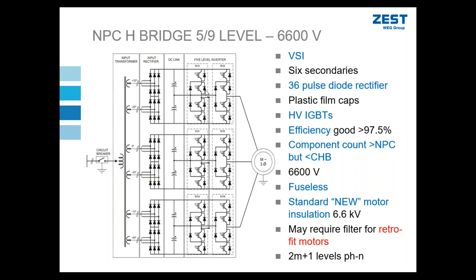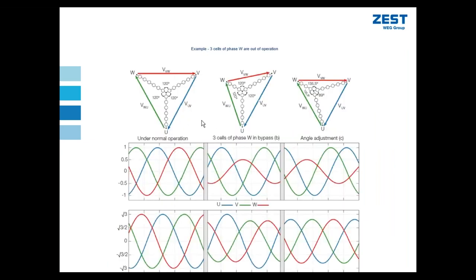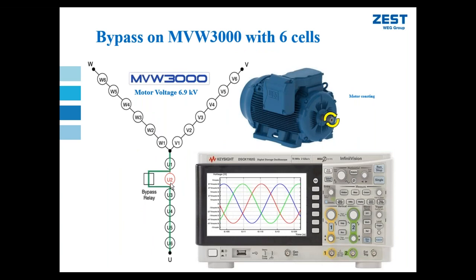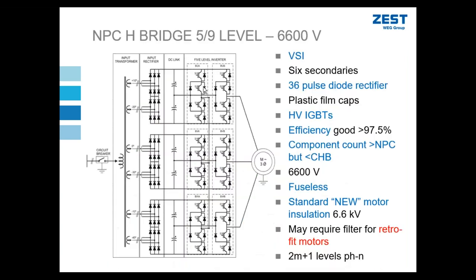Also, I don't have a simple bypass. The bypass here is simple because I'm only bypassing a 690 volt power cell. Here, I'm dealing with much higher voltages. Here, you're talking more than 3000 volts, so I'd need a more robust bypass circuit as well. It's not commercially practical to add redundancy to this hybrid topology. But that being said, this topology is inherently more reliable as a total system solution.